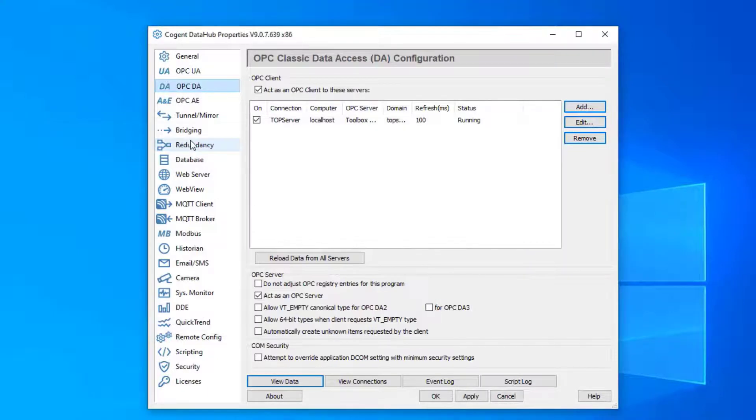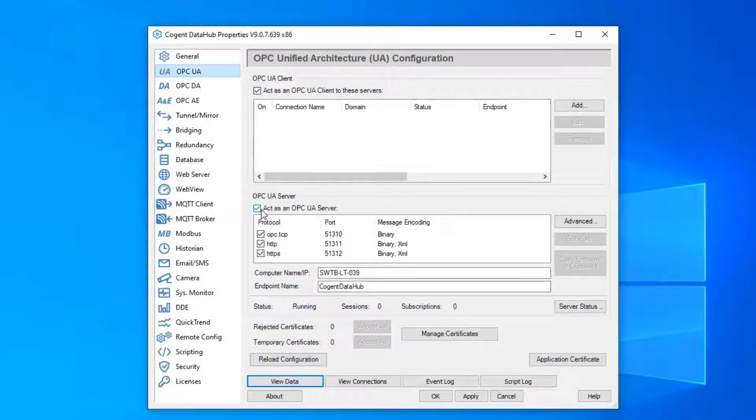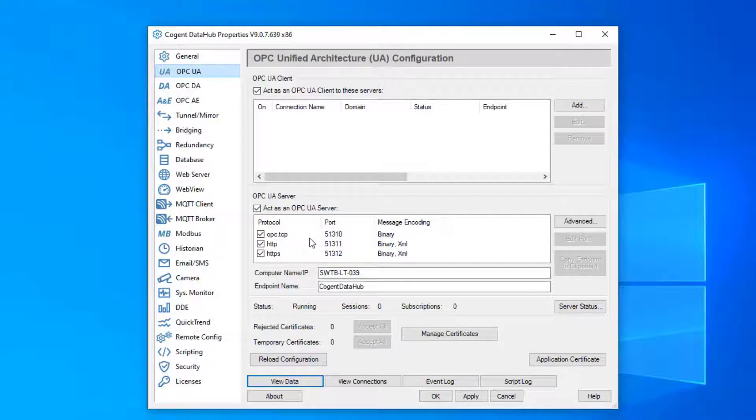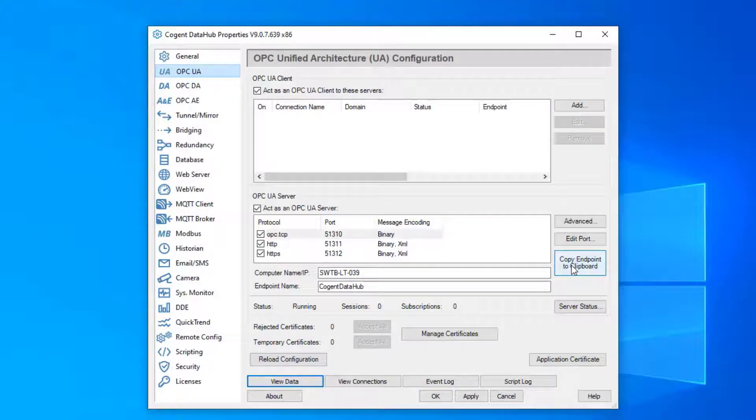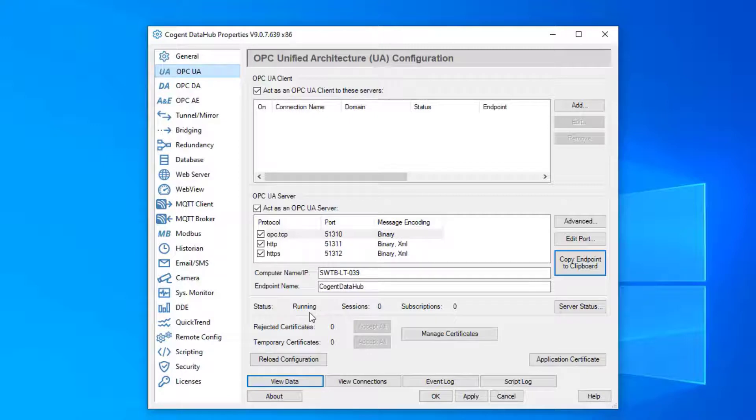Now we just need data hub to serve this data to a UA client. So if we go to our UA section, the first thing we need to do is make sure that data hub is acting as a UA server. We are listening on these different ports and I'm going to use the OPC TCP endpoint. I can copy that to a clipboard; I'll need that later. You can see here it says the status of the server is running. That's a good sign. That means we should be able to connect to it.